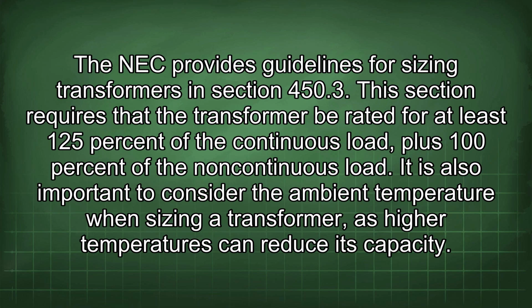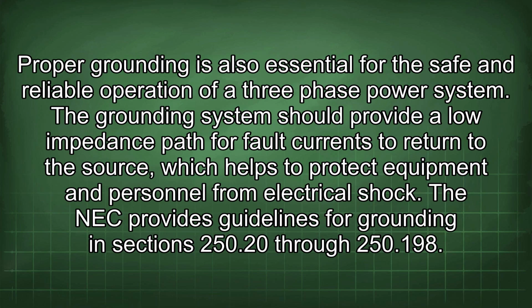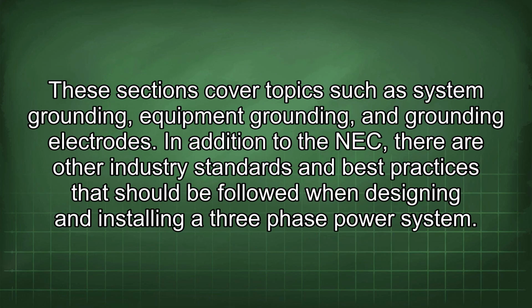Proper grounding is also essential for the safe and reliable operation of a 3-phase power system. The grounding system should provide a low impedance path for fault currents to return to the source, which helps to protect equipment and personnel from electrical shock. The NEC provides guidelines for grounding in sections 250.20 through 250.198. These sections cover topics such as system grounding, equipment grounding, and grounding electrodes.